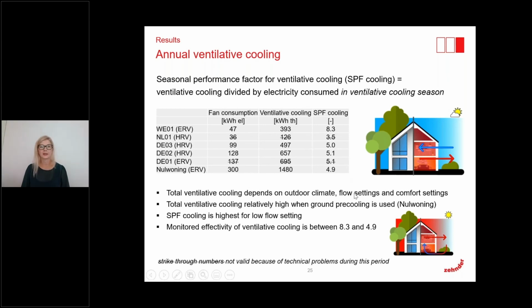What is also interesting to see is that total ventilative cooling is relatively high when ground precooling is used. We can see that those kilowatt hours for this thermal energy are significantly higher than for the systems without ground preheating or pre-cooling, sorry. In that way, we are also getting a better indoor climate in the summertime, and this is an advantage because we are then taking the energy back to the ground as well with this solution. So we are using what the environment is giving us in the most clever way.